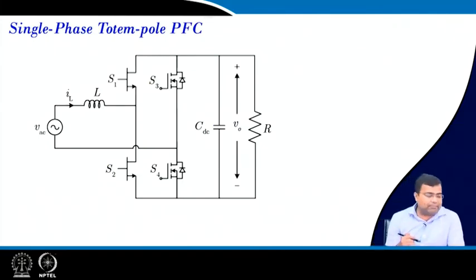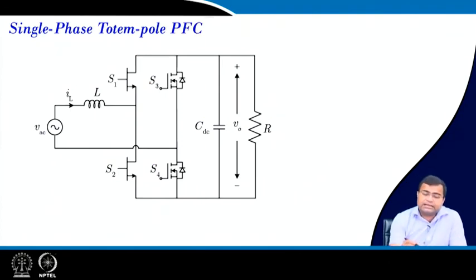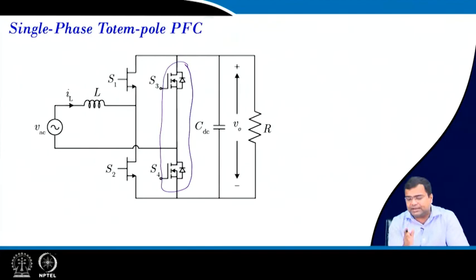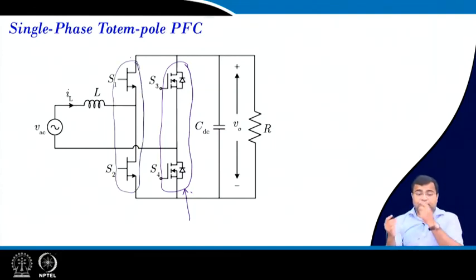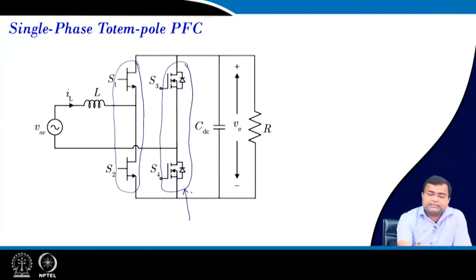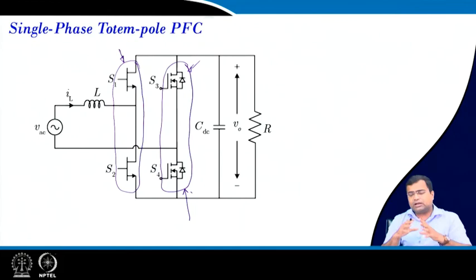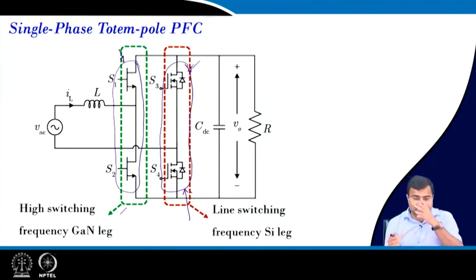For the totem pole PFC, we replace the lossy diode bridge with MOSFETs. With wide-bandgap devices, we can replace one half-bridge leg with MOSFETs whose body diodes function like diodes. The low-frequency leg operates at line frequency (50 or 60 Hz using silicon devices), while the high-frequency leg uses wide-bandgap devices — GaN or SiC — operating at much higher switching frequencies in a boost-type operation.